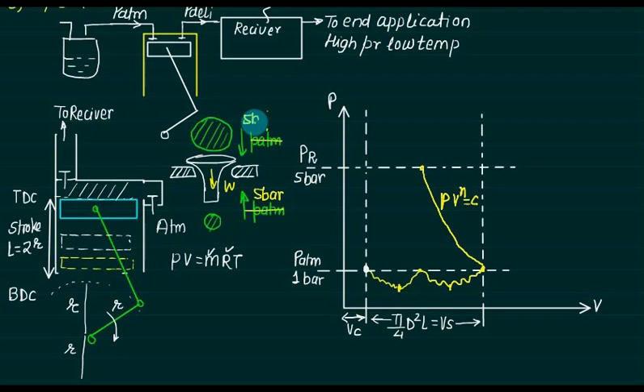Whereas the top pressure is also 5 bar. But here and because of the weight, the downward force is more as compared to upward. So the valve will not open. So it will continue to move upward the same line. Now the pressure is slightly more than 5 bar, so that this pressure will become something 5.5 bar for example. So that the upward force will increase and downward force will remain same. At this point the delivery valve opens. As soon as the delivery valve opens, some of the air will leave and again it will close.